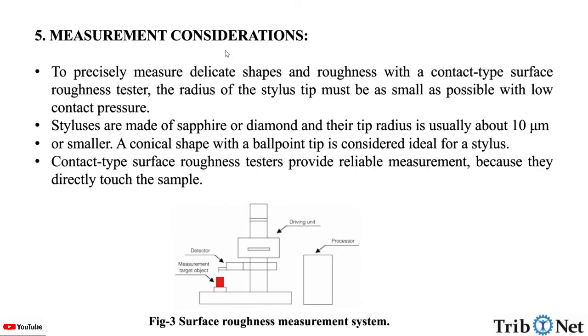What are the measurement considerations in the stylus instrument? To precisely measure delicate shapes and roughness with a contact type surface roughness tester, the radius of the stylus tip must be as small as possible with low contact pressure.